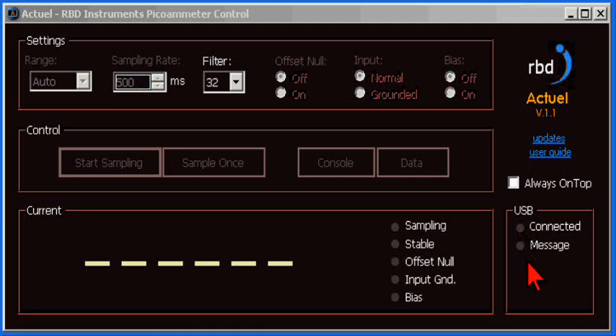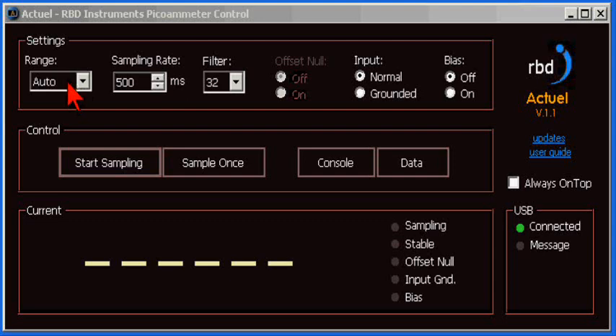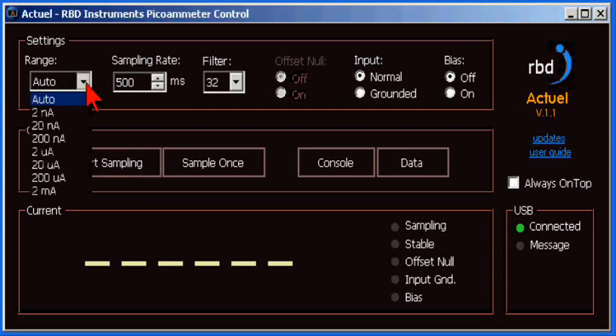The settings that you can control include the range, which can be set to auto, or fixed ranges between 2 nanoamps up to 2 milliamps. I'll set it to 2 microamps for now.